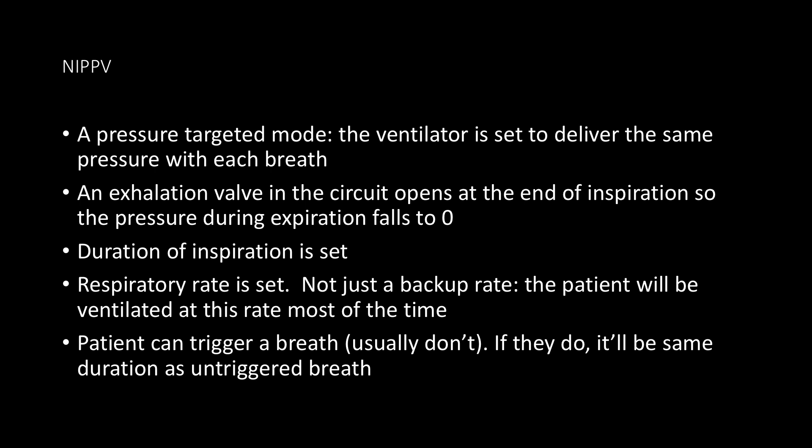NIPPV is a pressure-targeted mode — the ventilator is set to deliver the same pressure with each breath. An exhalation valve in the circuit opens at the end of inspiration, so the pressure during expiration falls to zero. The duration of inspiration is set, and the respiratory rate is set. This is not just a backup rate — the patient will be ventilated at this rate most of the time. Patients can trigger a breath, although they usually don't; if they do, it will be the same duration as an untriggered breath.